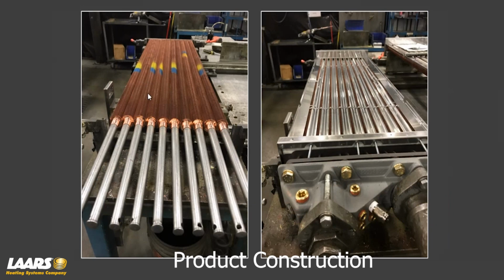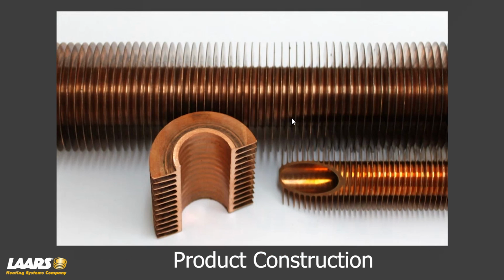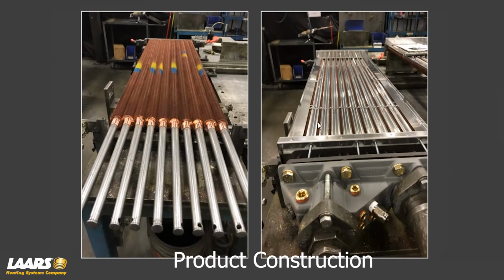So the heat exchanger, they'll line up the tubes. They'll put the header plates on. They'll pressure test everything and then put the inlet-outlet headers on, as well as the V-baffles. The V-baffles sit in position over the grooves. What they're there for is they want to be able to absorb the BTUs traveling through these fins. So if you put 2 fins side by side, you don't want all your flue gases traveling through the fins. You want them to wrap around those fins or around those tubes and then out the gap.